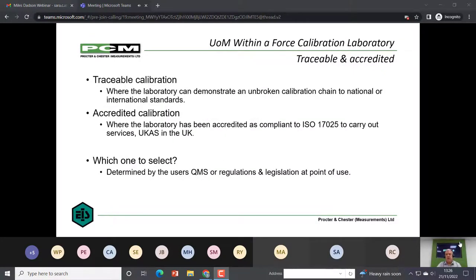One of the main questions we get is, why would I go for traceable and why would I go for accredited? There are some subtle differences. On a traceable calibration, you effectively need to demonstrate an unbroken chain to national, international standards of all the instrumentation that you're using to generate that calibration.